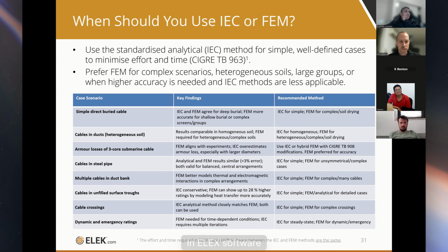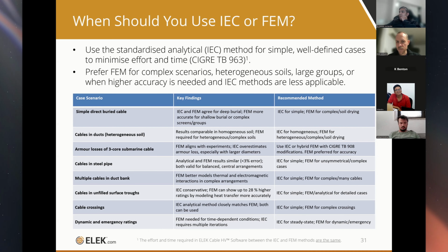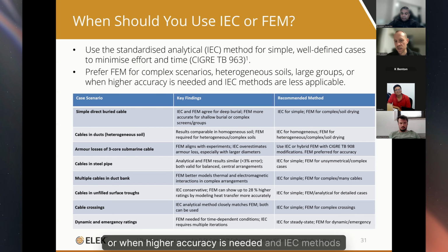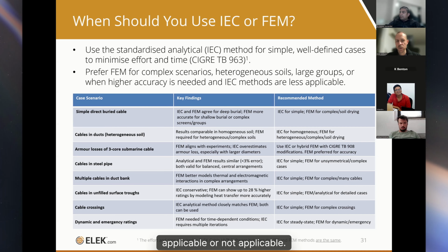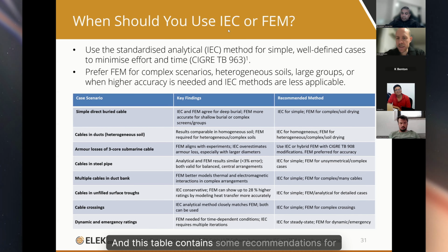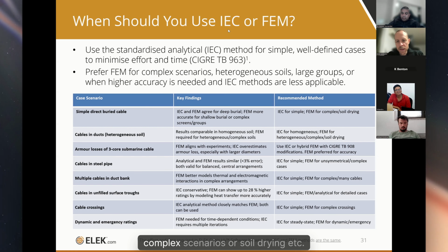in ELEK software. For complex scenarios, you should use FEM for heterogeneous soils, complex soil structures, large groups of cables, or when higher accuracy is needed and IEC methods are less applicable or not applicable. And this table contains some recommendations for when you should use IEC or FEM, where there's complex scenarios or soil drying, etc. So you can use that as a reference.